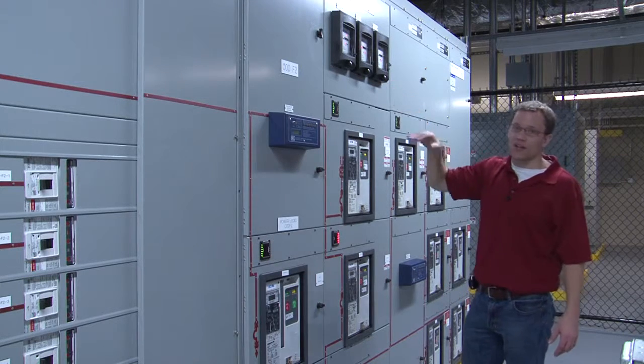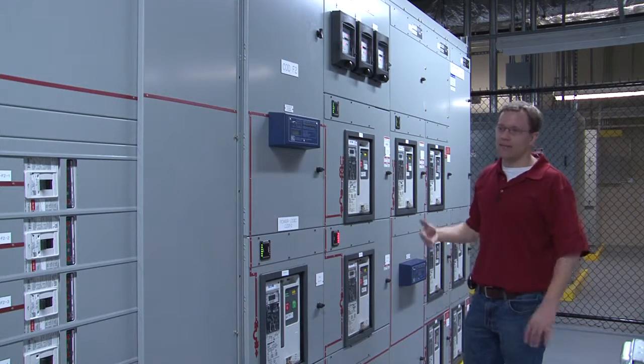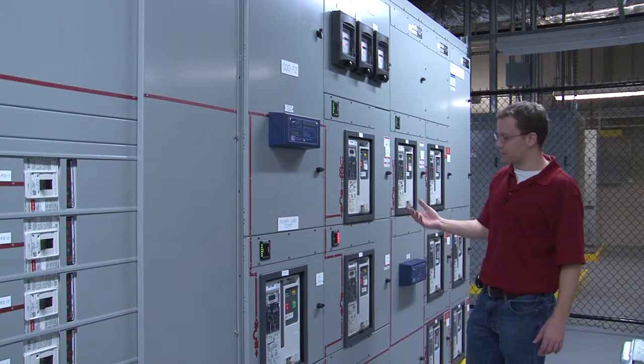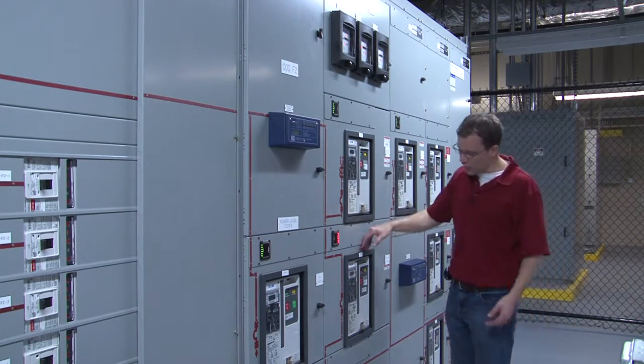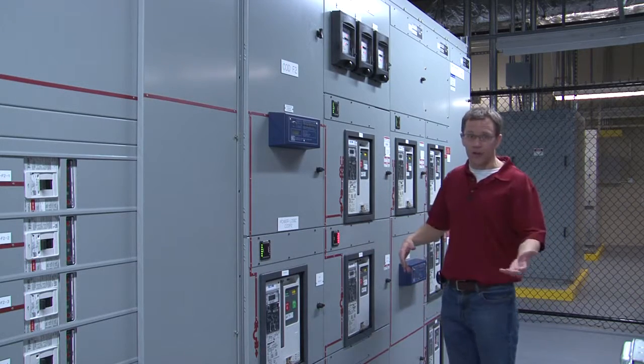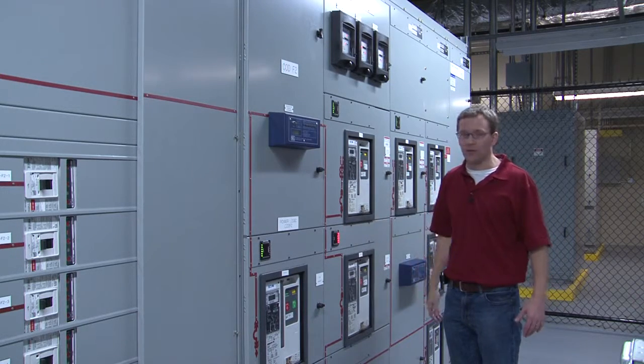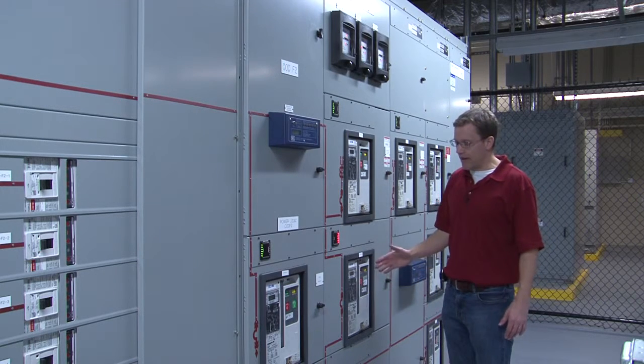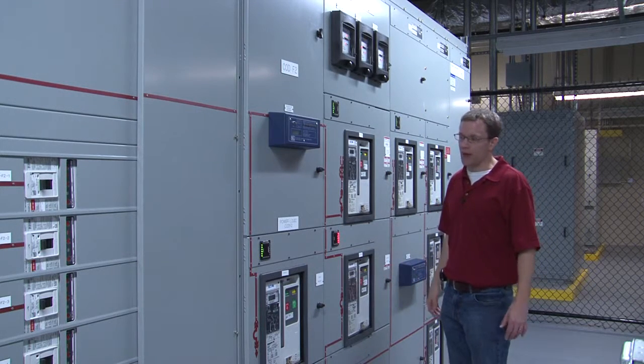The other two breakers allow live line dead bus closures, so that if the isolation breaker is closed but the modules are all off and you wanted to go to maintenance bypass, you could do that. It would close this breaker and open that breaker. And then likewise in the opposite direction.